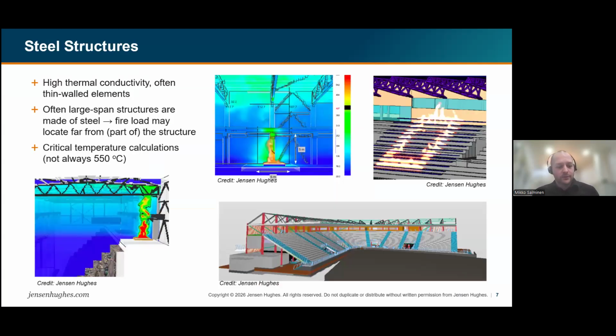Okay, then moving to different materials, starting from steel structures. Steel structures are often applied in structural fire engineering because usually they have only about 15 minutes fire resistance in standard fire when unprotected, and that's why they often need applied passive fire protection to achieve 30 minutes, 60 minutes, or whatever higher classification.